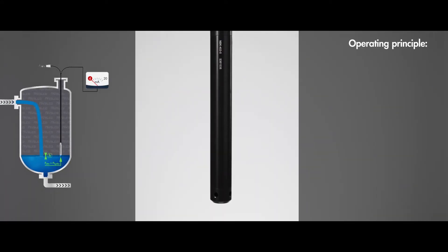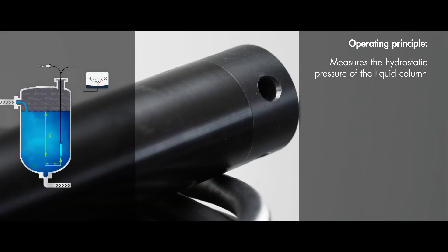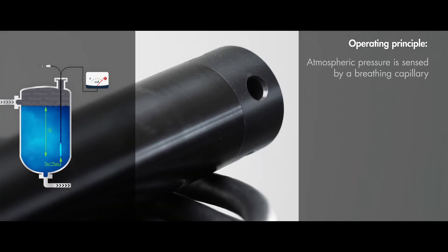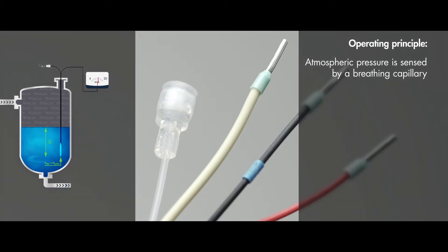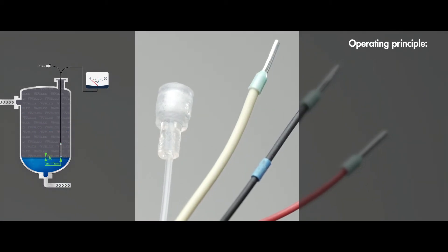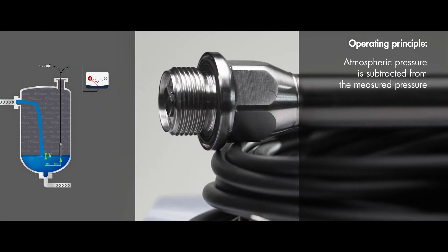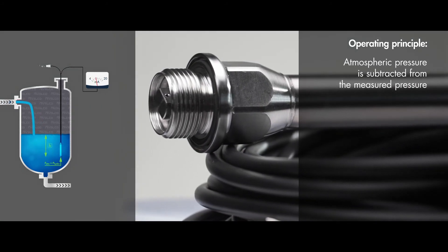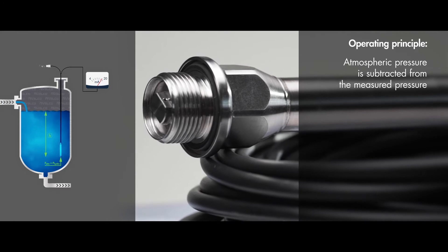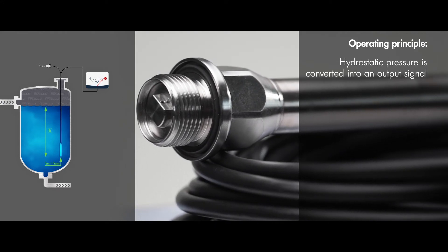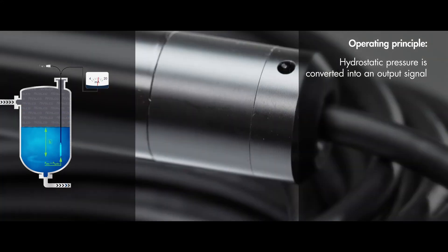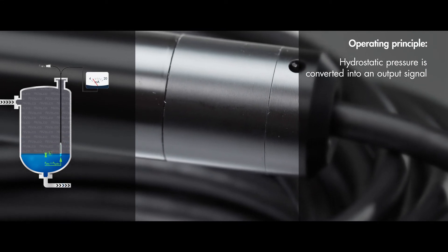Operating Principle. The pressure sensor at the bottom of the probe measures the hydrostatic pressure of the liquid column above it and compares with the atmospheric pressure. The atmospheric pressure is led to the sensor through a breathing capillary. The atmospheric pressure is subtracted from the measured pressure to get the hydrostatic pressure, which is proportional to the height of the liquid column. The electronics converts the sensor's signal into an output signal.